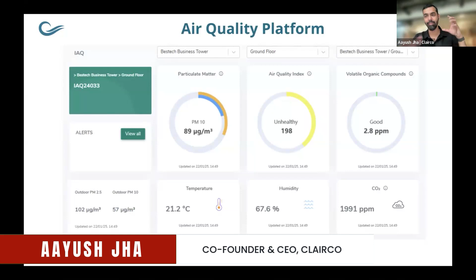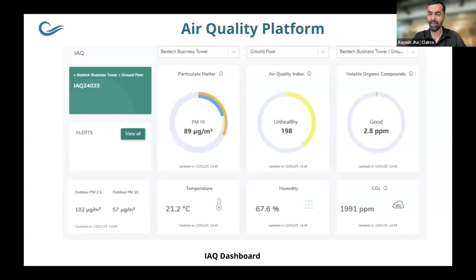That is where the direction of all BMSs should be going, towards a singular system using multiple sensors and gaining intelligence, instead of just using information for that particular system. For example, if a filter is clogged, is that automatically sending information to the vendor to send a quote or the next shipment of filters? That's not happening. Ultimately everything ends up on the BMS operator's shoulders, which is unfortunate.